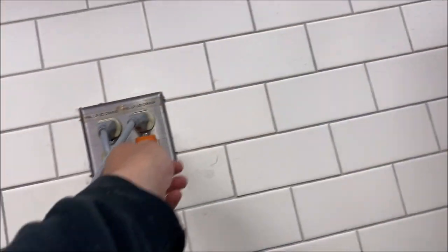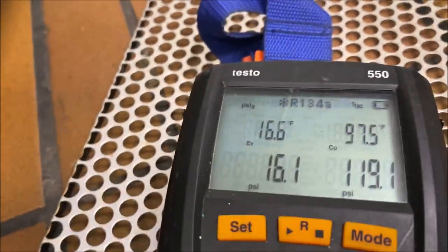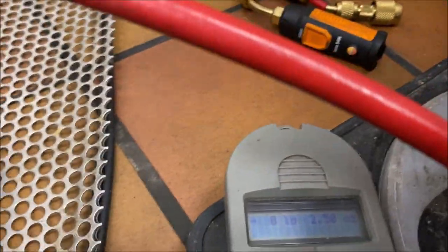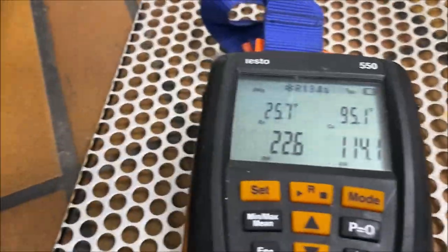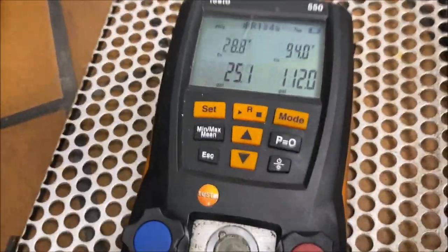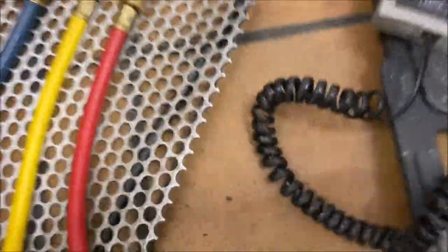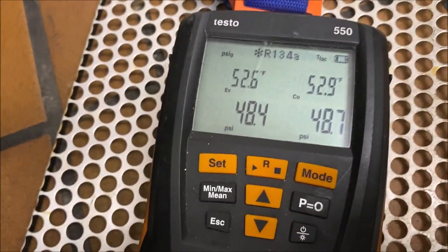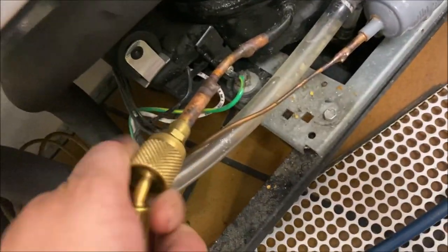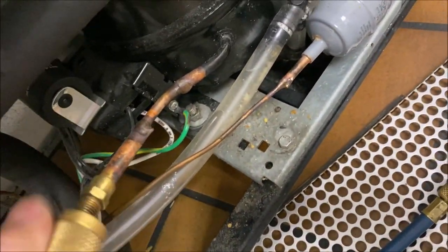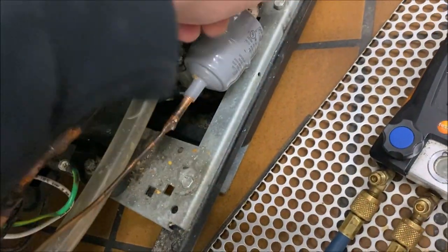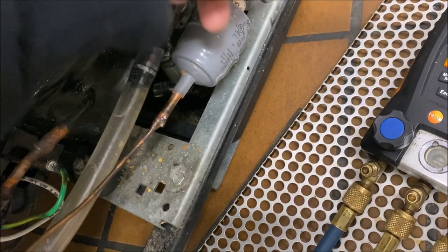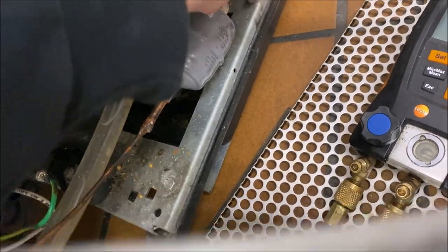Okay, so I'm going to unplug the unit now. And what that's going to do is equalize the system. Okay, and we'll see if we have enough pressure in here to do our leak test. And we're low two and a half ounces, so we got a pretty small leak here. So we equalized around 48 PSI. So I'm going to go ahead and do a quick leak test here. If I can't find it, we'll pump her up with nitrogen.